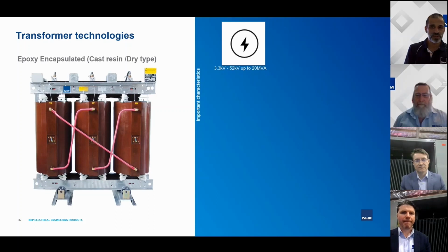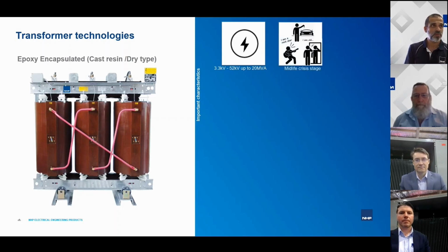Thanks, Nick. Yeah, so as Nick mentioned, we're just talking high level about some of the main features of dry type transformers. Or firstly, the transformers we're referring to here are cast resin dry types, because there are various types of dry type transformers, but we're specifically talking about cast resin transformers. Now, generally in the industry, you will come across ratings of voltages between 3.3 kV to maybe about 52 kV, and up to about 20 MVA in size, which is getting quite large, but that's the ratings they get up to these days. Now, if you look at cast resin transformers, they have been around for a little while, even contrary to what some people might say or think. As we call it, they're probably going through a bit of midlife crisis. They're about the age of 30, 40 years, or probably approaching 50 in some cases, where they're getting into newer and more advanced technologies, which we'll talk about in the next few webinars.